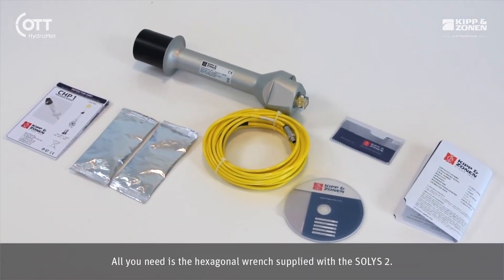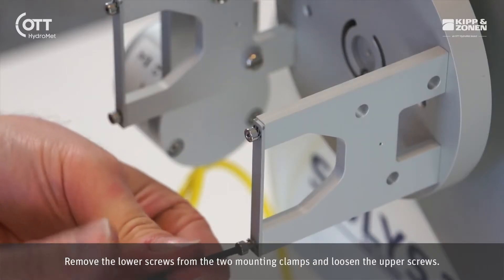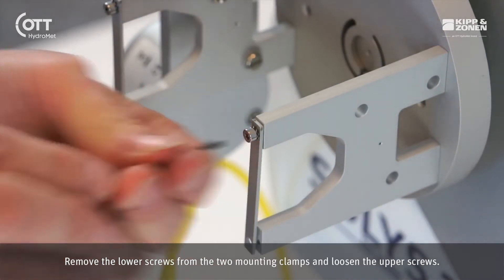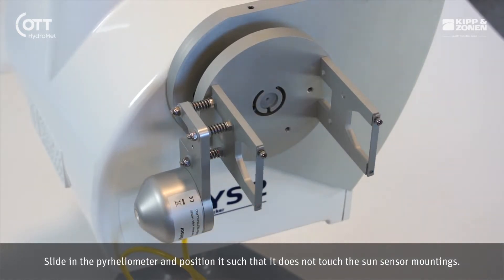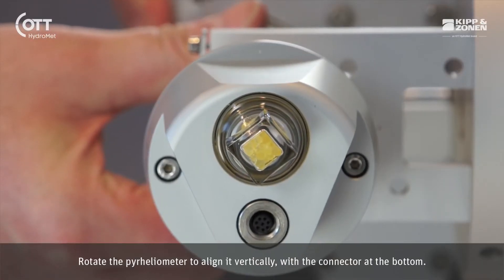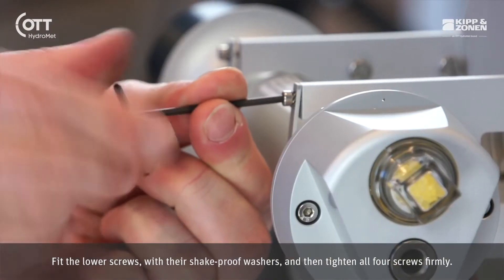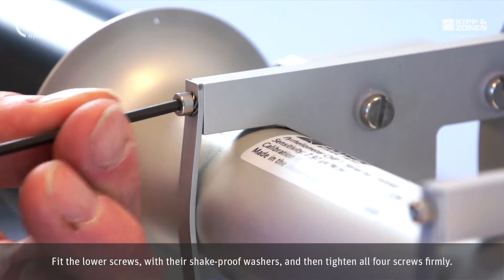All you need is the hexagonal wrench supplied with the SOLYS 2. Remove the lower screws from the two mounting clamps and loosen the upper screws. Slide in the pyrheliometer and position it such that it does not touch the Sun sensor mounting. Rotate the pyrheliometer to align it vertically with the connector at the bottom. Fit the lower screws with their shake-proof washers and then tighten all four screws firmly.